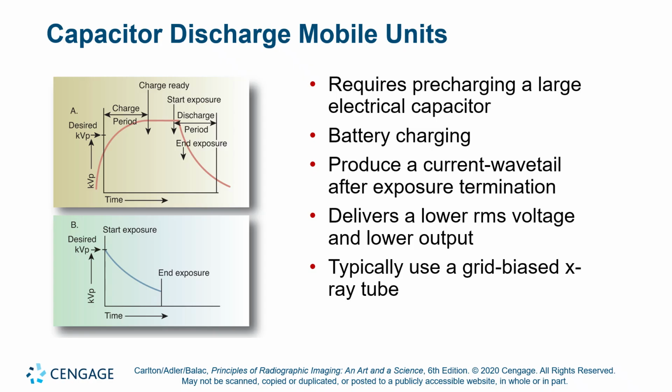All right, so this is the load up and the charging in these graphs. You pre-charge, right? And then usually there's some kind of indicator on your control panel that goes from red to green. When it turns green, that means your capacitors are fully charged and it's ready to expose. You've got to plug this thing into the wall to charge the capacitor arrays.